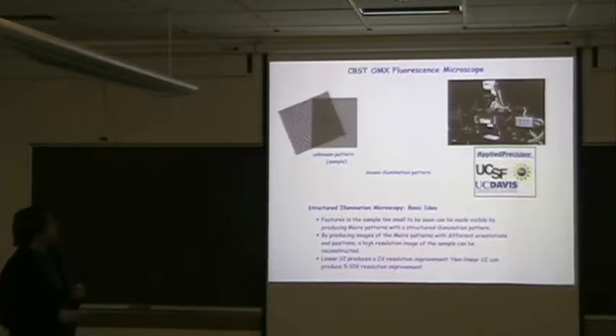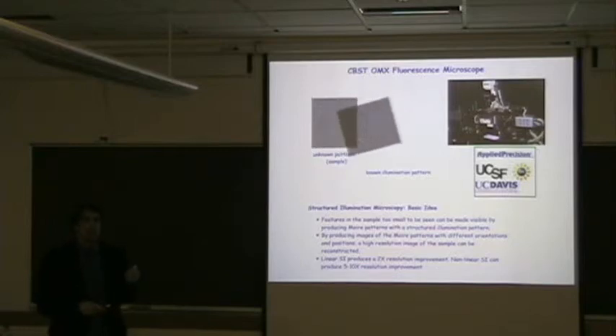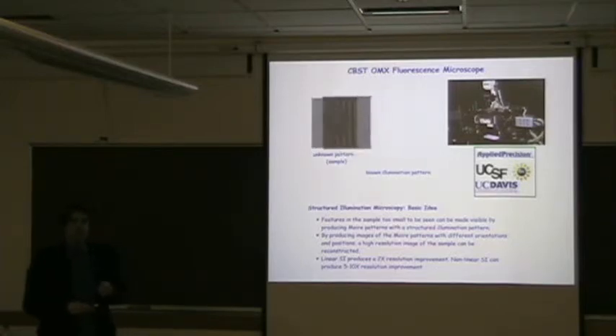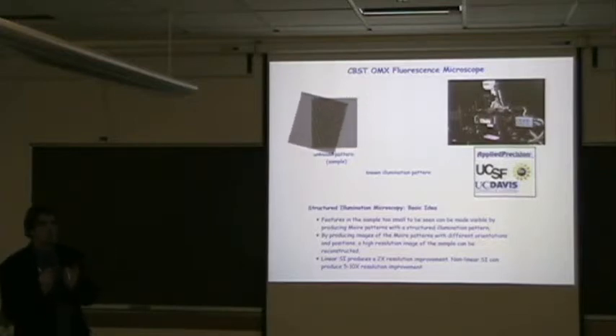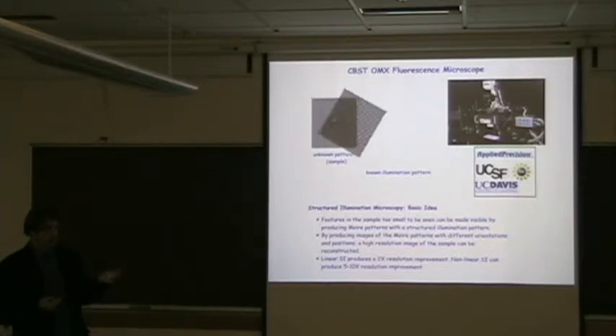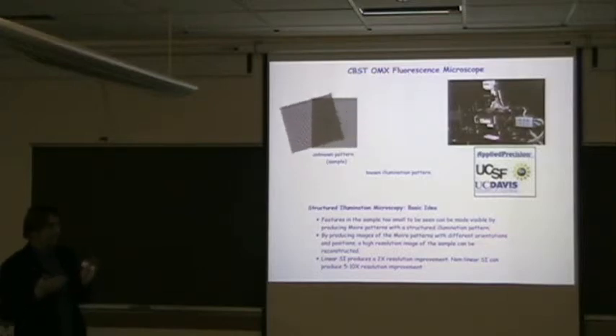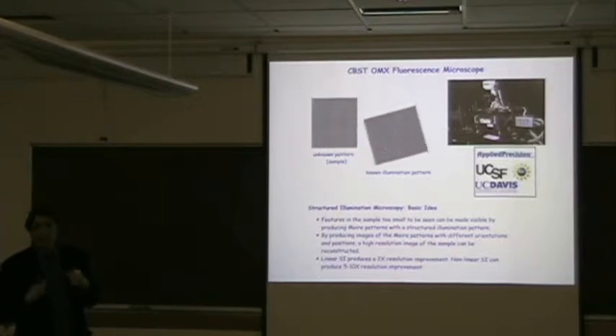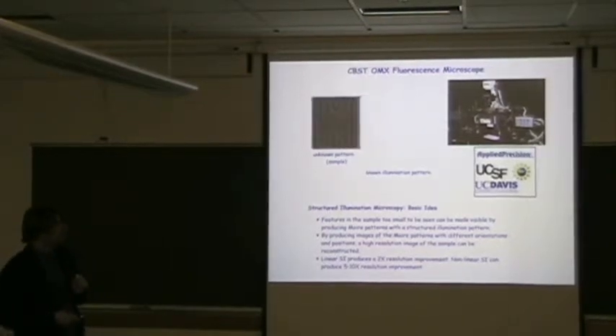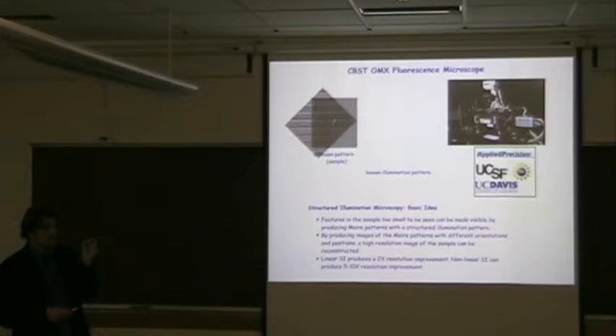Now, this technique here is using moire patterns, which are observed a lot in regular photography. Whenever you superimpose two patterns on top of each other, and you know that a CCD camera is a pixelated detector with a certain pattern, for example a shirt with patterns, you would see moire patterns in that image. Those moire patterns have a different frequency, usually lower frequencies, that can be measured. The high frequency, the small patterns, you cannot observe, but you can measure the low frequency patterns, like you see here. And this is what this instrument does.